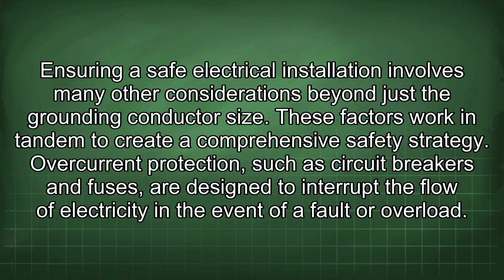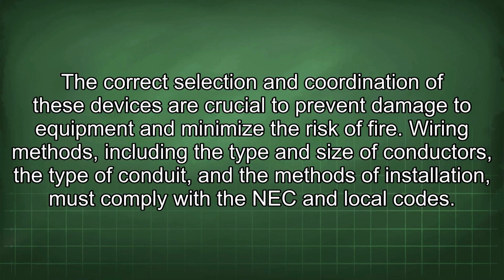Ensuring a safe electrical installation involves many other considerations beyond just the grounding conductor size. These factors work in tandem to create a comprehensive safety strategy. Overcurrent protection, such as circuit breakers and fuses, is designed to interrupt the flow of electricity in the event of a fault or overload. The correct selection and coordination of these devices are crucial to prevent damage to equipment and minimize the risk of fire.